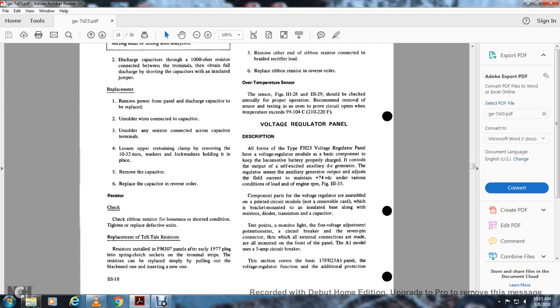Replacement. Remove the power from the panel. Discharge the capacitor to be replaced, with unsoldered wires disconnected from the capacitor and any resistors connected across the capacitor terminals. Loosen the upper capacitor clamp by removing the 10-32 nuts, washer and lock washer holding it in place. Remove the capacitor. Replace the capacitor in reverse order.